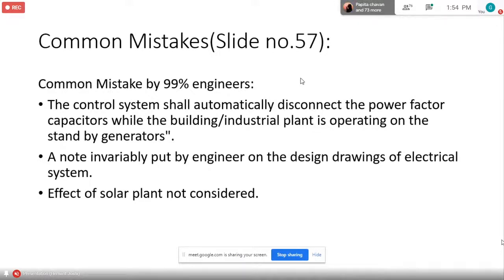But generally what happens is the generator supply and the main supply are on different breakers. The power factor sensing for the capacitor correction is provided on the mains breaker. So when the generator comes in, the power factor correction unit doesn't come into the picture at all.